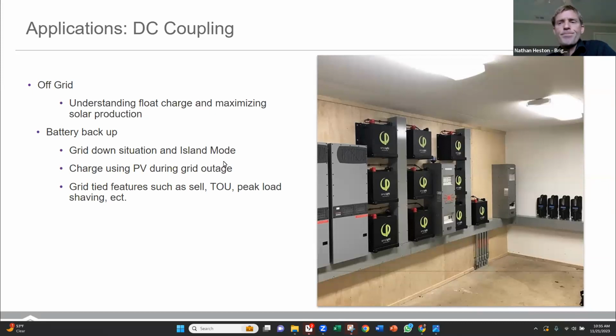Daniel, do you have more comments on that? I would mention that some of the offerings by Sol-Ark 30K and the 60K can get higher voltages, but those are in battery enclosures that prevent user access to some of those high voltage bus bars. The other thing to point out is that the 30K by Sol-Ark is a 208 three-phase system. You've got 480 for the 60K, and we do have battery offerings for those if you are interested in commercial and industrial. But for typical home systems where you're looking at two-phase or split-phase power, it's almost always 48-volt systems, and that's due to safety, and those safety considerations are built into the regulations.